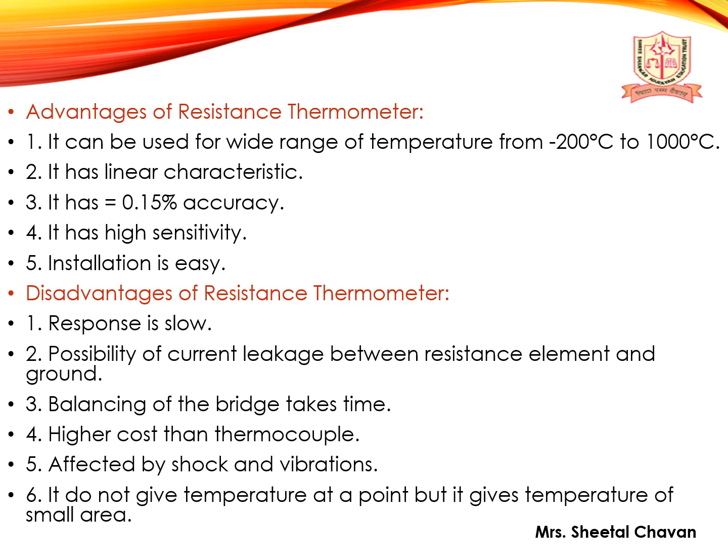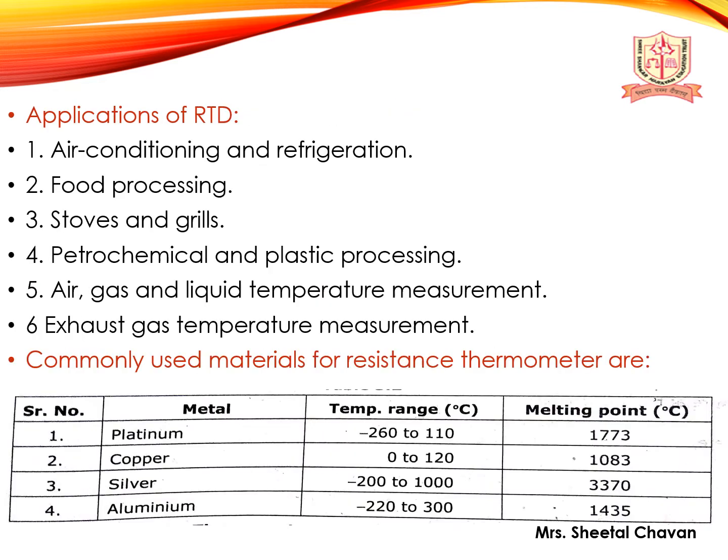Disadvantages of resistance thermometer are: response is slow, possibility of current leakage between the resistance element and ground, balancing of the bridge takes time, higher cost than thermocouple, it is affected by shock and vibration. It does not give the temperature at a point, but it gives the temperature of small area.